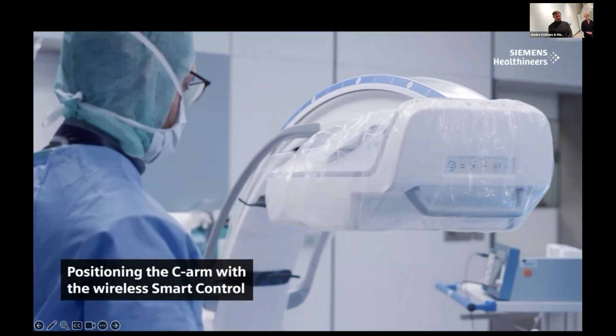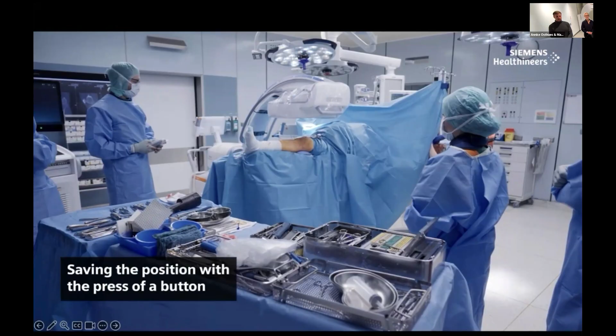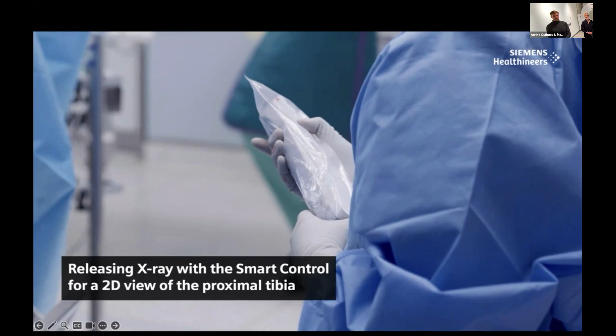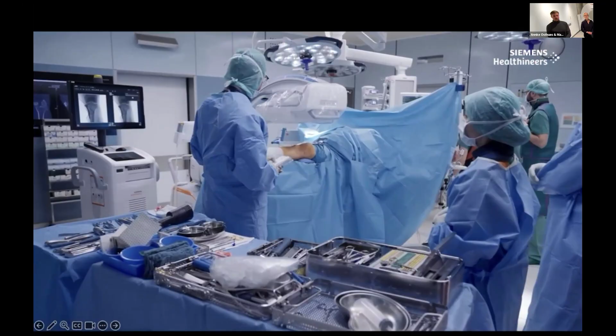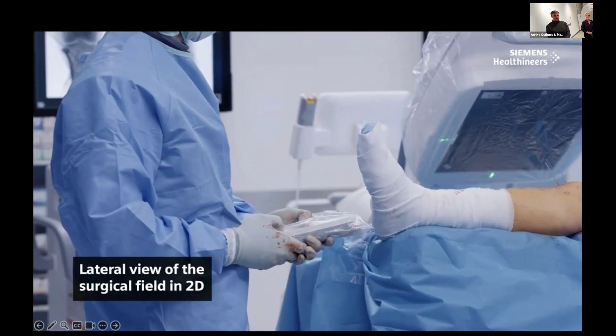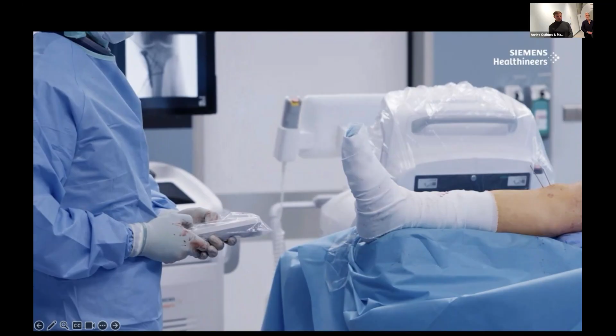taking the C-arm onto the OR table over the leg of the patient. And now he's positioning the C-arm at the right position and saving the position with a press of a button, storing this position. After doing so, he's handing it back to the nurse. The nurse is then releasing X-ray with a smart control. This could be done by the surgeon as well, but he's working on the leg itself, so he's handing it over to the nurse. Now he's back to the instrument, to the smart control, and reaching out to start for the next position, the lateral view. And this is going on for a while.